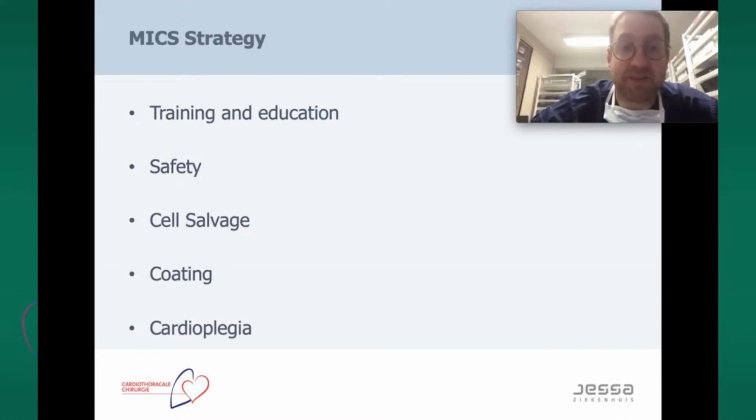We work with bubble sensors, level sensors, aortic clamp. So if there is an issue you can handle, you need to have backup mechanisms, safety mechanisms. Even if you have, let's say, an issue once in 2 years, there always will be people standing at the sidelines who tell you, I told you so. So be aware, always have backup mechanisms.